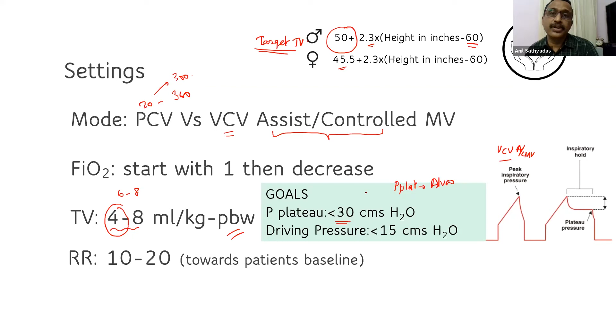Full tidal volume, 500 ml set, 500 ml to be given. Okay. So how will the ventilator come to know? That is usually by the drop in pressure that is generated because of the patient's spontaneous breathing, inspiration. Any spontaneous inspiration would produce negative pressure in the circuit, and that negativity is sensed by the ventilator.